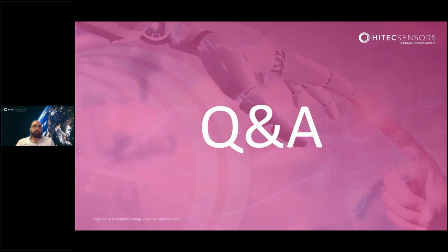Another question: how does strain gauge sensitivity compare between foil and semiconductor technologies, and what trade-offs exist in real-world robotic applications? As I explained in the presentation, semiconductors have a gauge factor of about 150, which is typically 75 times more sensitive than a regular foil strain gauge. But they have their downfalls too, with temperature compensation, and they're more sensitive to vibration as well. With our proprietary methods, we're able to compensate them properly. It has to do with the installation and preparation for those sensors to act properly within the system and give the high accuracy requirements that the customer would need.